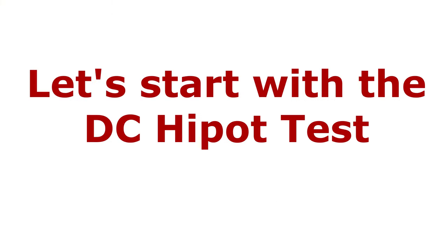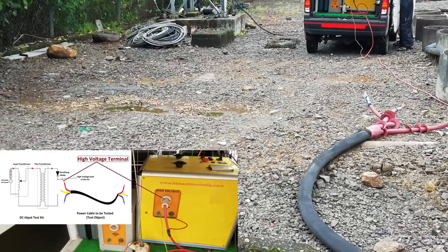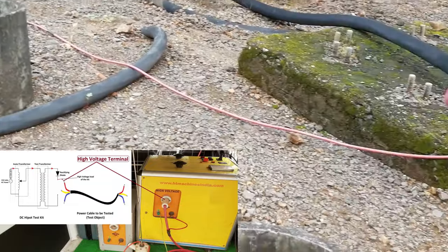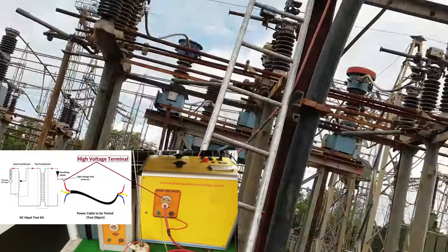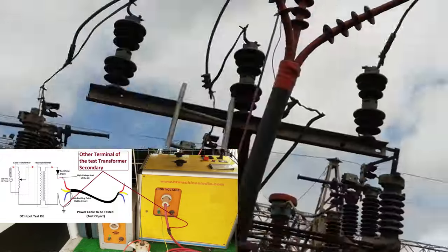Now let's start with the DC hipot test. First of all, the cable to be tested is isolated completely from both ends, and all three phases of the cable are discharged using earth rods. This makes the cable free of any possible residual charges and safe to work on. Now this high voltage terminal — which is the secondary terminal of the test transformer of the kit — is connected to the phase conductor of the cable on which the test is to be done, and this other terminal and the cable armor are connected to the ground.